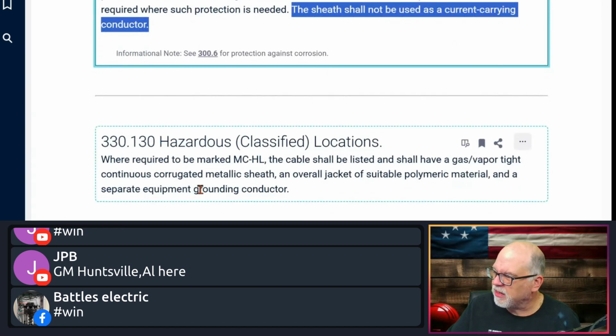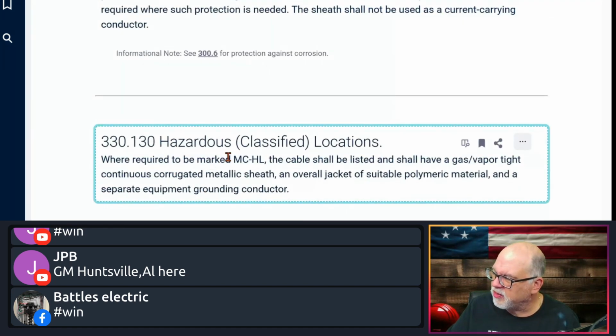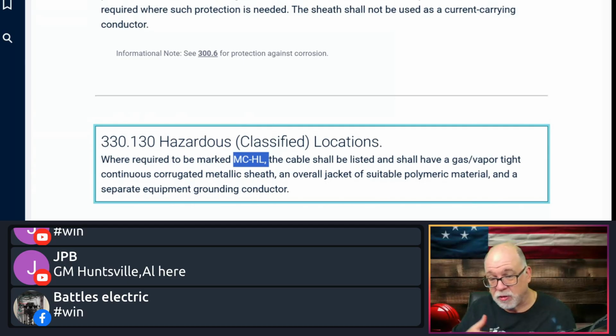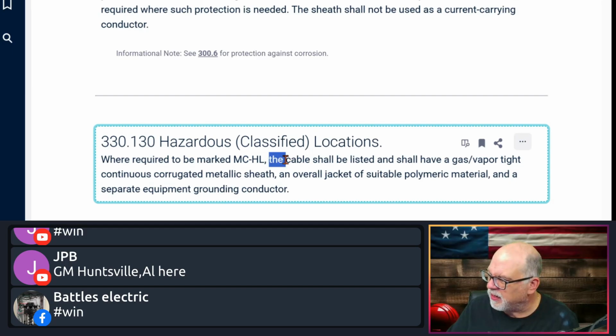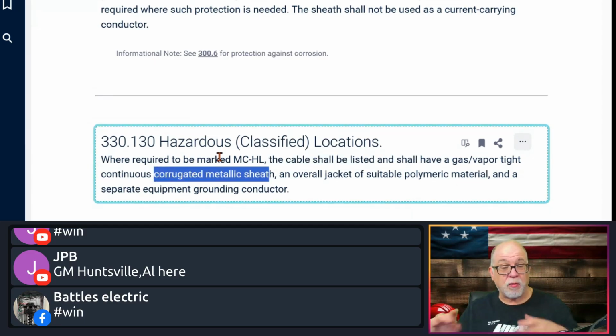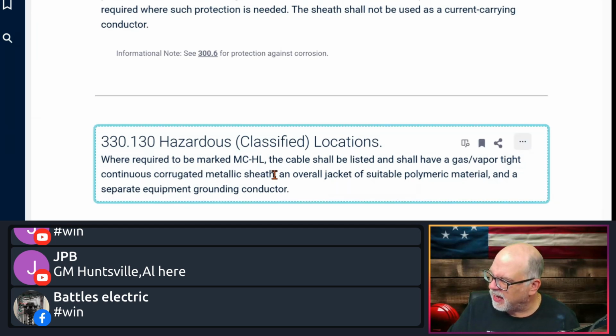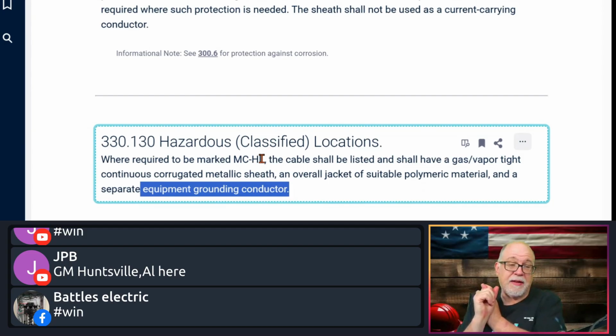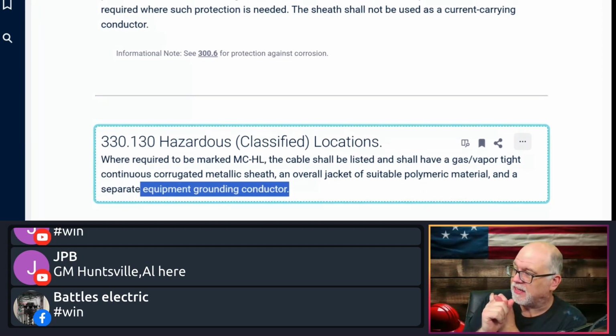All right. Hazardous location, it says we're required to be marked MCHL. You heard me talk about that earlier. If you have MC and it's going to be used in a hazardous classified location, then it typically would have an MCHL marking or designation. It says the cable shall be listed and shall have a gas/vapor tight continuous corrugated metal sheathing. So that is why I told you earlier that most hazardous locations are going to want a corrugated type of MC rather than an interlocked. Okay. And it says it has an overall jacket of suitable polymeric material and a separate equipment grounding conductor. So in the construction of an MCHL, it's very important to understand that it has to have a polymeric material.